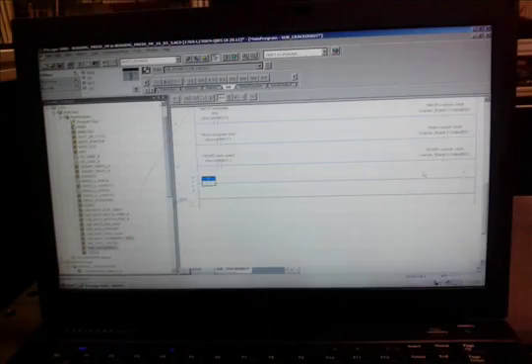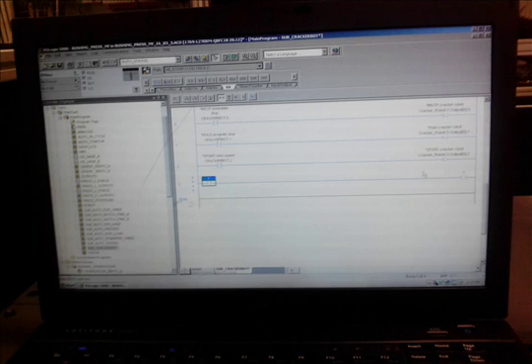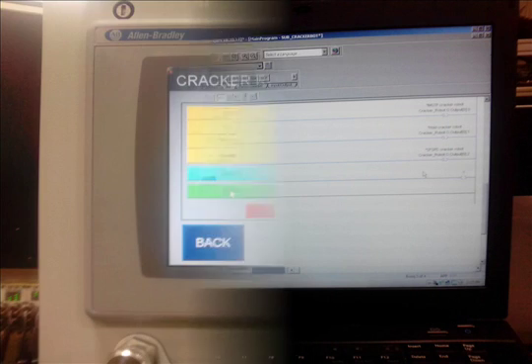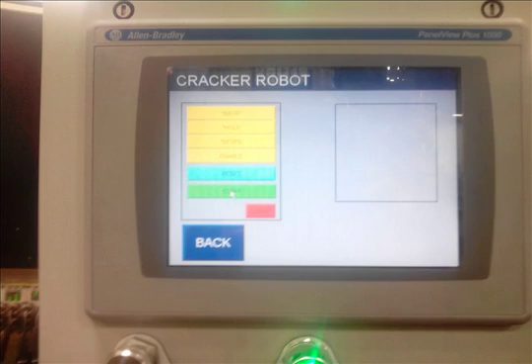And if you step into the warning zone, it will slow down. So the repairer will want to do some changes to the machine. So he will step into the area close to the robot. So when that happens, it will slow down. And if you cross beyond this limit, you will cause the robot to do an immediate stop. So that's the logic, the Control Logix, and that's the HMI screen.